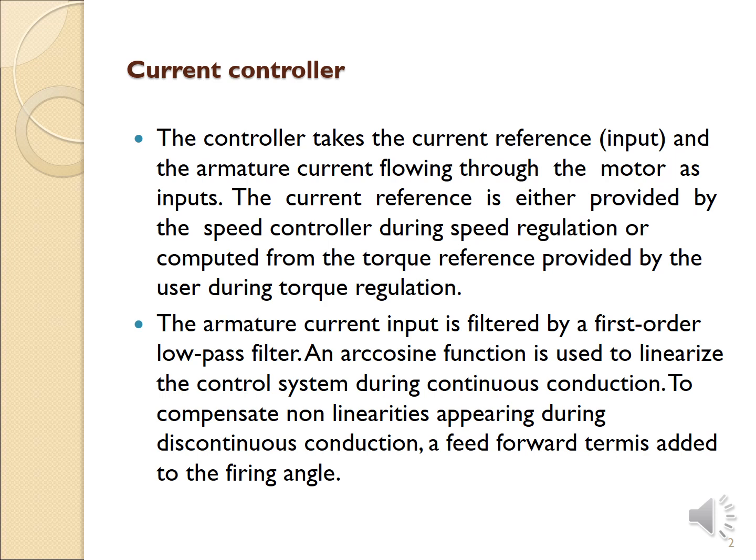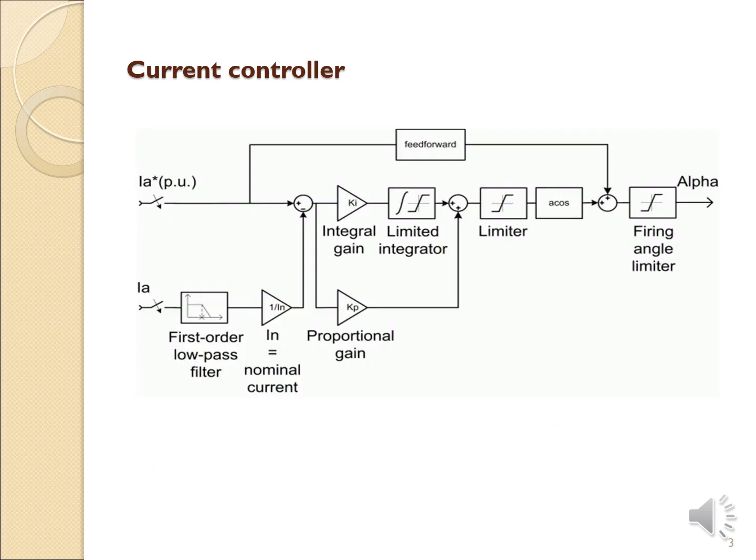The armature current input is filtered by a first-order low-pass filter, and an arccosine function is used to linearize the control system during continuous conduction conditions. To compensate for non-linearities appearing during discontinuous conduction, a feed-forward term is added to the firing angle.